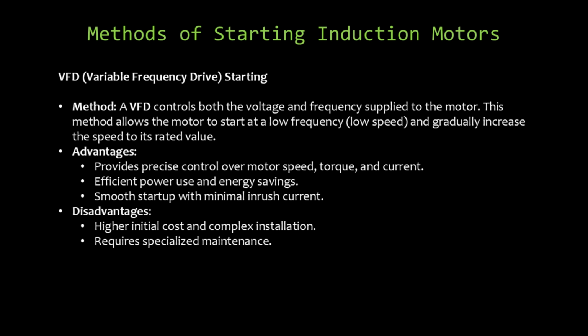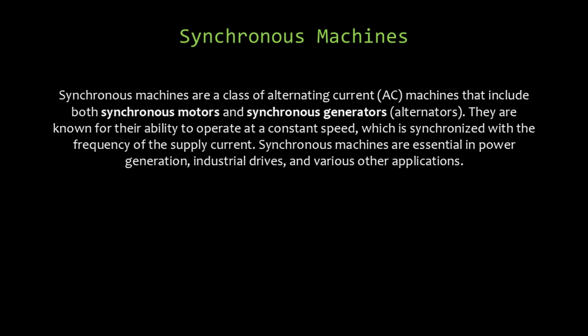The variable frequency drive represents a sophisticated starting method. VFDs control both voltage and frequency supplied to the motor, allowing it to start at a low frequency and gradually increase to rated speed. This approach provides precise control over motor speed, torque, and current. It offers efficient power use, energy savings, and a smooth startup with minimal inrush current, though at a higher initial cost. Let's explore synchronous machines.